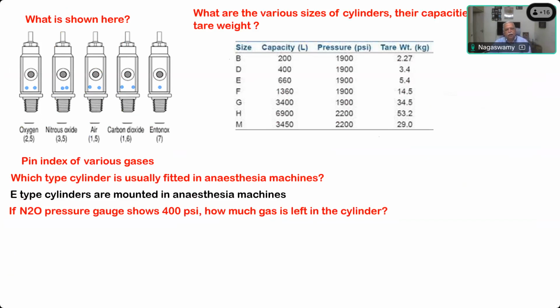Very good. And supposing the pressure starts dropping and comes to 400 psi, what will be the amount of gas left in it? Why did the earlier nitrous oxide yoke assembly never have a pressure gauge? It is not reliable for nitrous oxide, sir. Why? Because it measures only the vapor pressure, and that depends on temperature. It is in the liquid form.